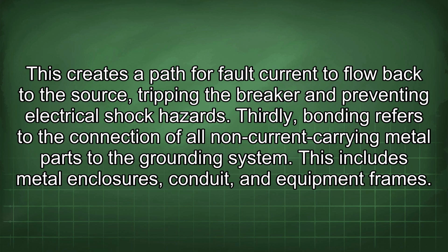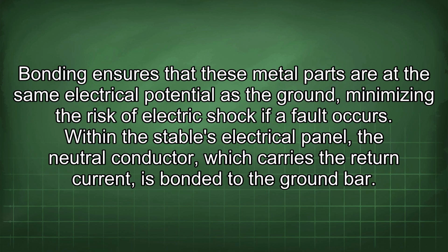Thirdly, bonding refers to the connection of all non-current carrying metal parts to the grounding system. This includes metal enclosures, conduit, and equipment frames. Bonding ensures that these metal parts are at the same electrical potential as the ground, minimizing the risk of electric shock if a fault occurs.